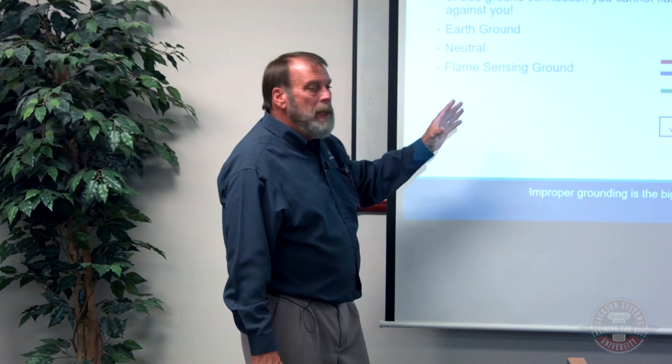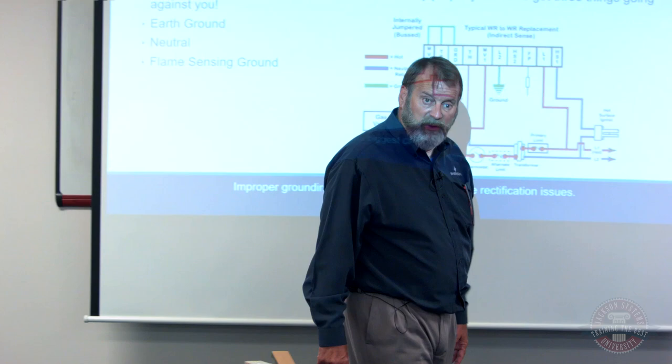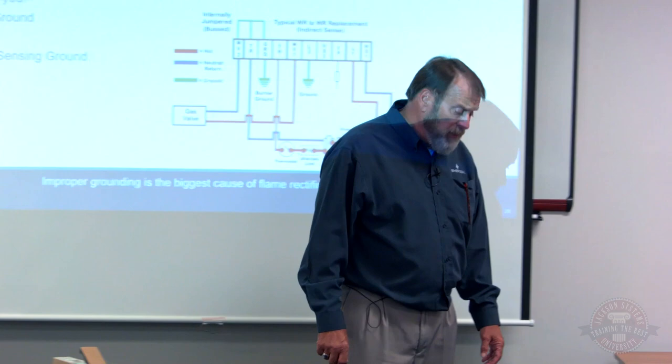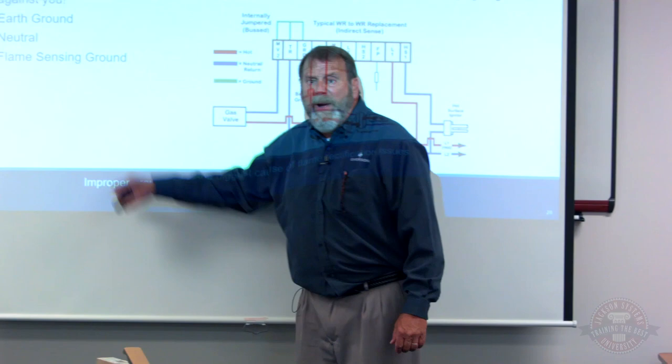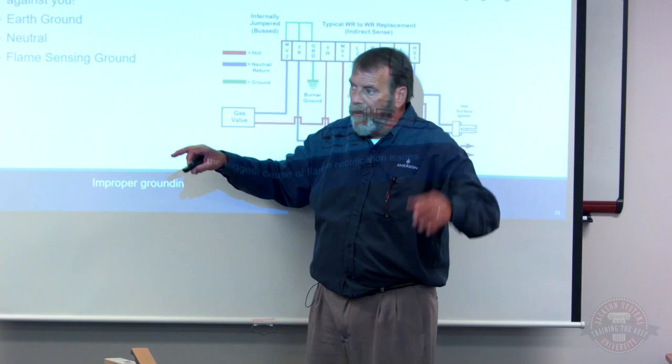Grounding, and I can tell you this, guys, because myself and my team answer those phone calls. I got 14 people answering the calls when you guys call in. 400 to 500 calls, and a lot of the ground issues, a lot of the flame rectification issues, all has to do with ground. Drives you nuts. And the problem is you got 3 grounds that could potentially be your issue. You got an earth ground, you got a neutral quasi ground, you got the flame sensing ground. Any one of those 3 can create the issue.